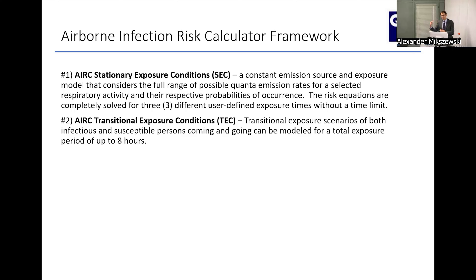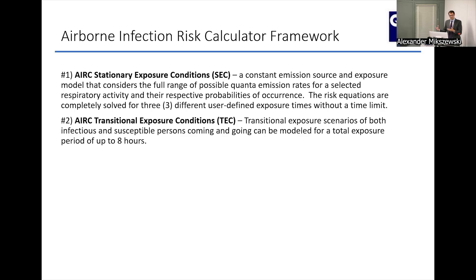We also included a numerical solution version for Transitional Exposure Conditions, which addresses the problem of a non-constant source. Say I'm talking here for 15 or 20 minutes, expiring some virus-laden aerosols, and then I leave and those are lingering in the room. This version of the tool allows that to be evaluated. For example, in a dentist office, a patient comes in, is treated, and leaves. How long should that room be flushed before someone else can reoccupy? That was the real goal of that specific model.